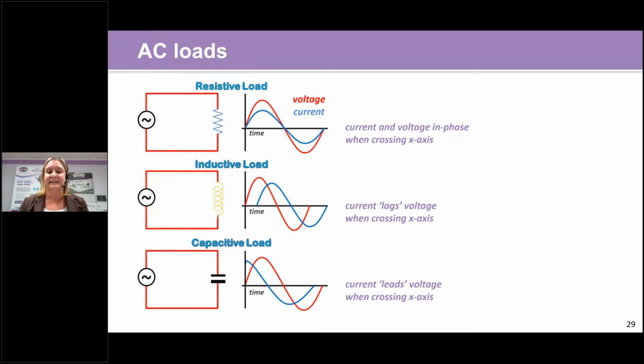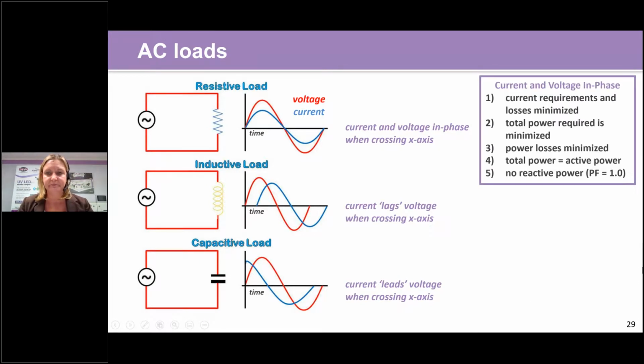This is an efficient circuit, but most equipment is not a resistive load. It's either inductive, most of them are inductive, or some of them are capacitive. For the inductive load, we can see that the current lags the voltage when crossing the x-axis. So if this is time, the axis here where the y and the x cross, that's 0. So the voltage is actually crossing 0 first, and then the current crosses, so it lags it. In a capacitive circuit, it's the opposite.